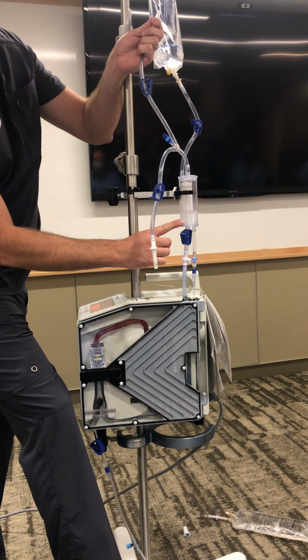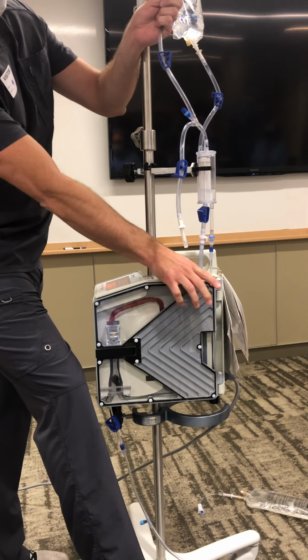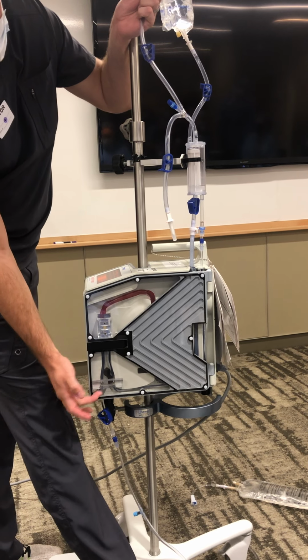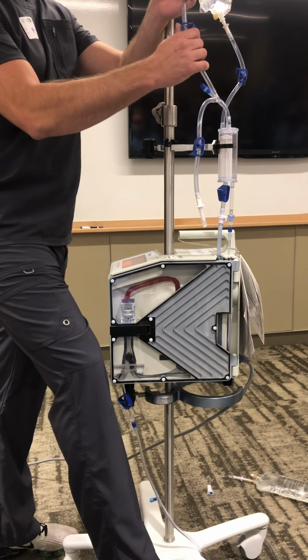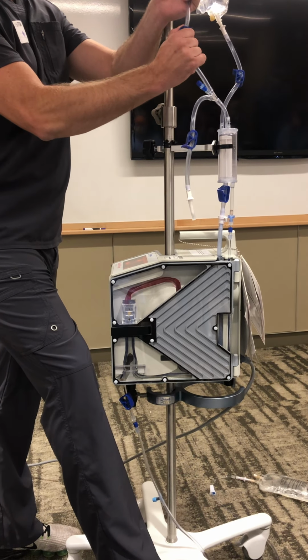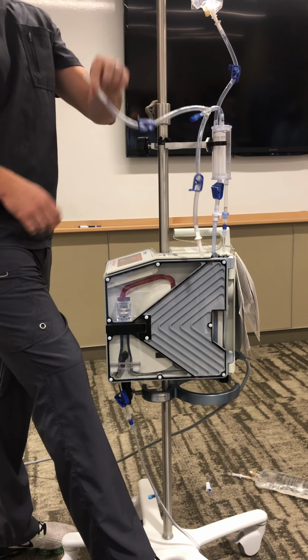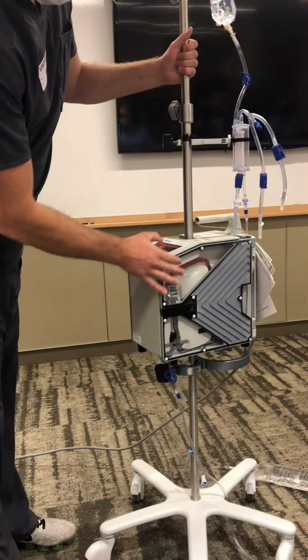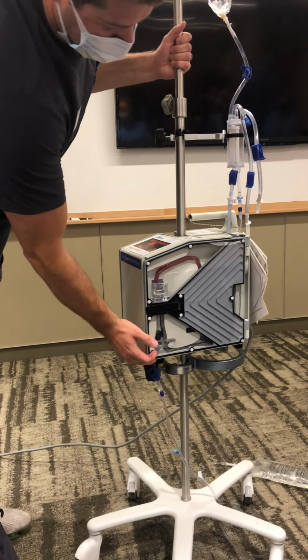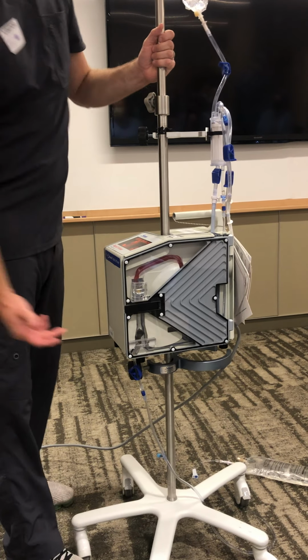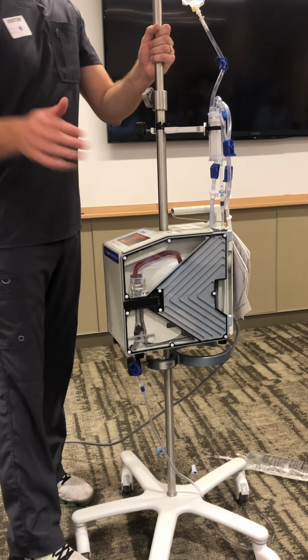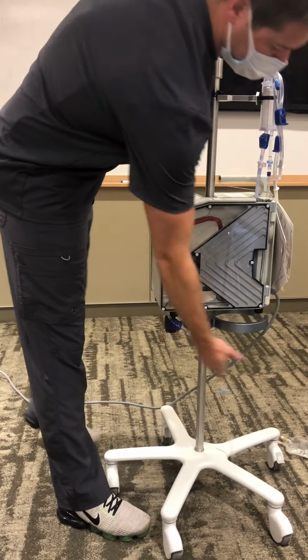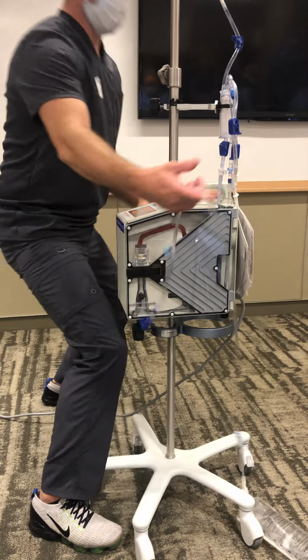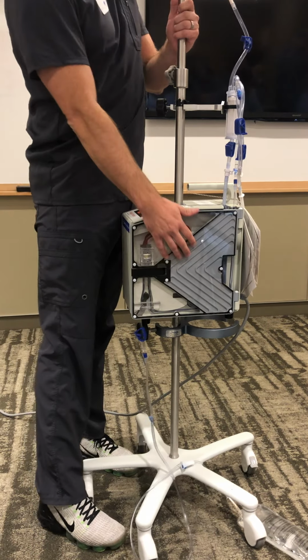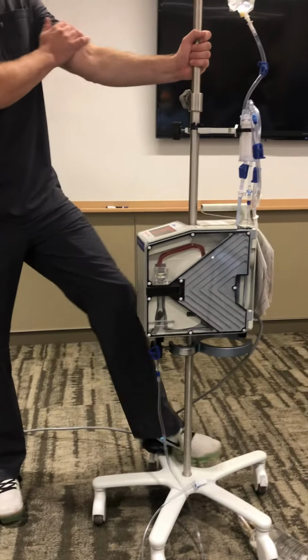Watch as the fluid starts to run out and air hits this sensor right here. What happens down here in this corner with the patient safety feature? Did you guys see that? Anytime you have an alarm, especially an air alarm, our patient safety wand right here slides over and pinches off the patient line, containing all of the air in the internal tubing.